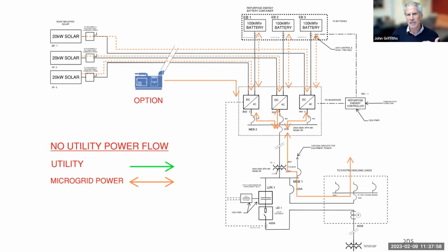Let's say it's 80 or 90% efficient. That's going to provide power to the building, and whatever's left over from the building load is going to charge the batteries. If it's connected to gas and gas is available, that's fine. But if you have a limited amount of diesel on site, you're going to get a lot more kilowatts from your gallon of diesel by connecting it to a hybrid inverter.